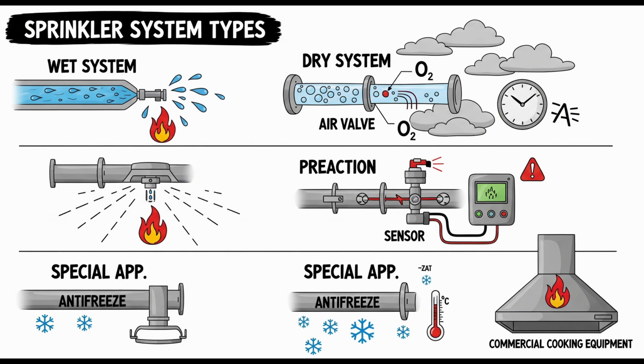That's the likely reason, yes. Freezer temperatures can fluctuate, and rate of rise detectors might be prone to nuisance alarms. You want reliable detection based on reaching a specific, fixed temperature threshold that indicates a real fire, and that threshold needs to be below the sprinkler's activation point to get the pipes filling first. Makes sense. But there's a significant exception mentioned.